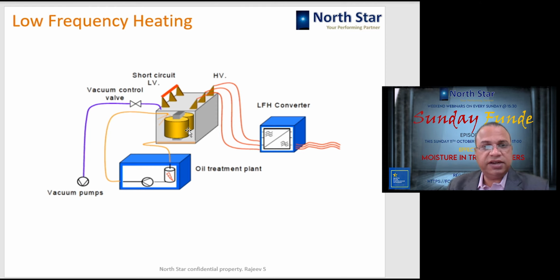As the windings get heated up, the insulation close to the winding also gets heated up, and when you spray the oil on such a hot winding, the moisture is going to come out because of these two factors. Then there is a vacuum suction system which sucks out the moisture released from the windings and insulation, and this moisture is thrown off. Of course, the LV is short circuited so that you have this heavy circulating current in the transformer. Okay, so this is low frequency heating.